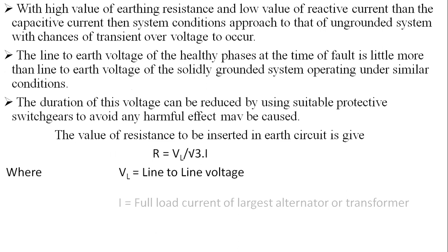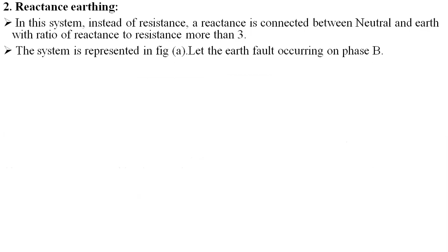Coming to reactance earthing. In this type, instead of resistance, a reactance is connected between the neutral and earth, with the ratio of reactance to resistance more than 3. The system is represented over here. Let the earth fault be occurring on phase B. In addition to the zero sequence impedance of the source and the faulty phase up to the point of fault, the fault current is dependent on the reactance. So by changing the value of the reactance, the fault current can be varied.